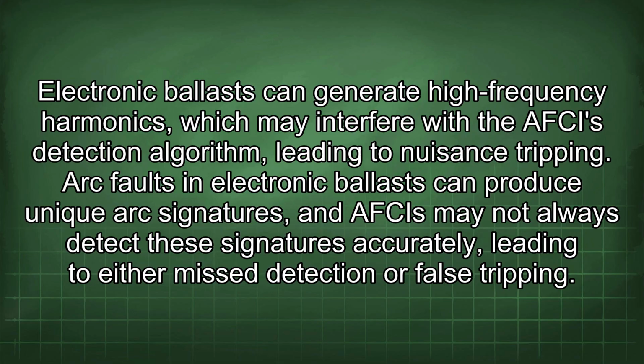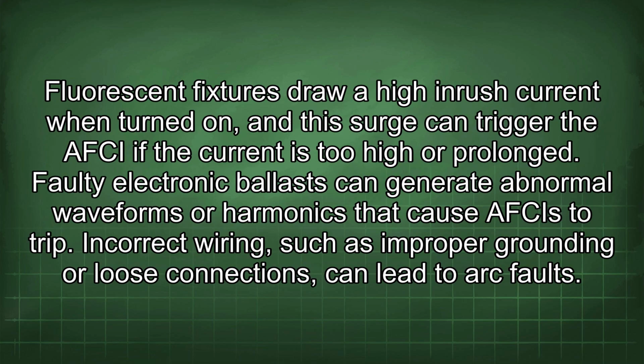Electronic ballasts can generate high-frequency harmonics, which may interfere with the AFCI's detection algorithm, leading to nuisance tripping. Arc faults in electronic ballasts can produce unique arc signatures, and AFCIs may not always detect these signatures accurately, leading to either missed detection or false tripping. Fluorescent fixtures draw a high inrush current when turned on, and this surge can trigger the AFCI if the current is too high or prolonged.